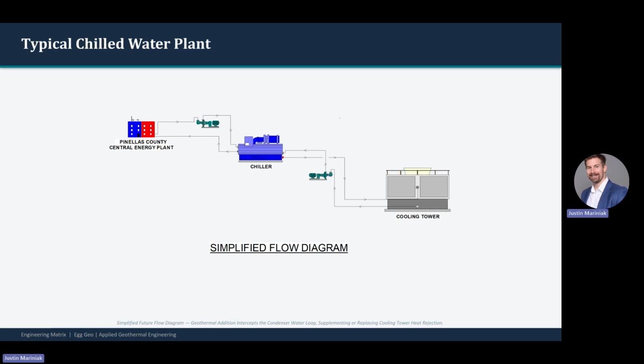Typical chilled water plant. Typical systems for buildings like this use water-cooled chillers with cooling towers. The building on the left rejects its heat to chilled water produced by the chiller. It uses a Carnot refrigeration cycle to extract heat from a space and put it in hotter areas. That heat is then rejected to a cooling tower that evaporates water to create a cooling effect. This process uses energy and consumes water to provide the cooling.